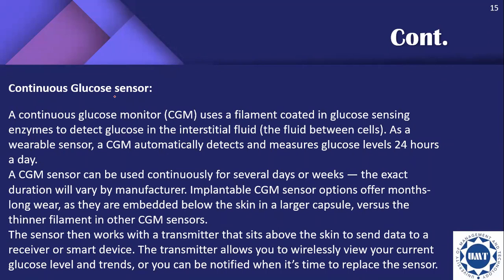A continuous glucose sensor (CGM) uses a monitor with a filament coated in glucose-sensing enzymes to detect glucose in the interstitial fluid. As a wearable sensor, it automatically detects glucose levels 24 hours a day and can be used continuously for several days or weeks, with implantable CGM options offering months-long wear.